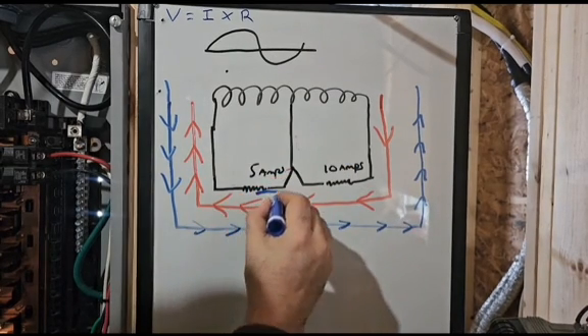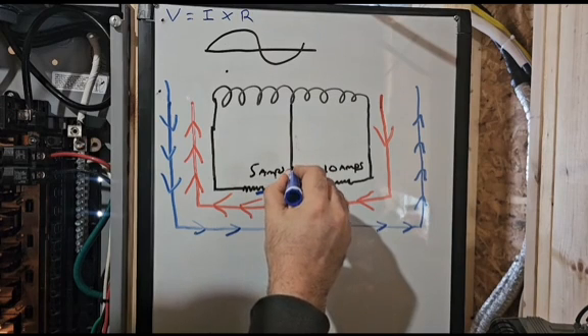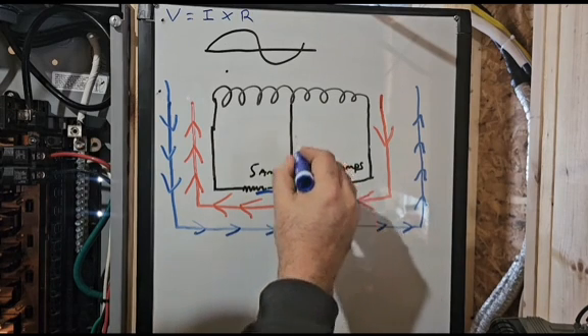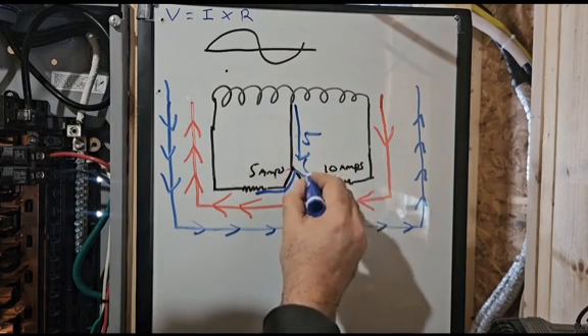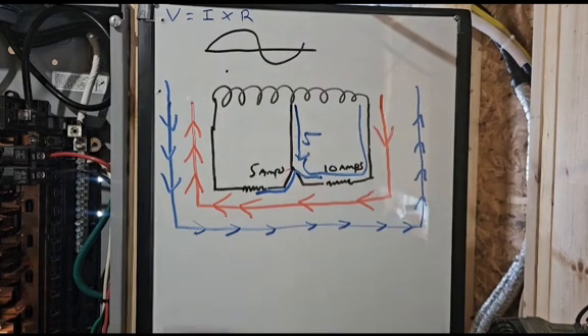When this 5 amps gets here and Ohm's Law calls for this needing 10 amps, this 5 amps in blue never goes on the neutral and will continue to this load. Then the neutral provides an extra 5 amps that goes through and back to the transformer that way.